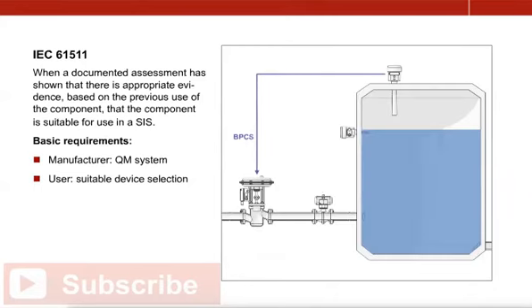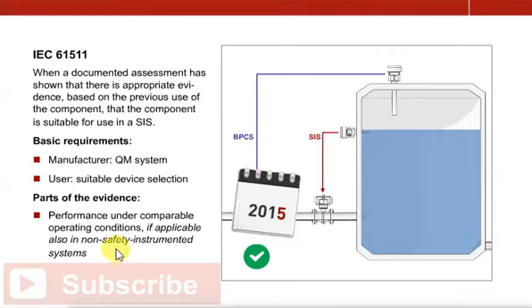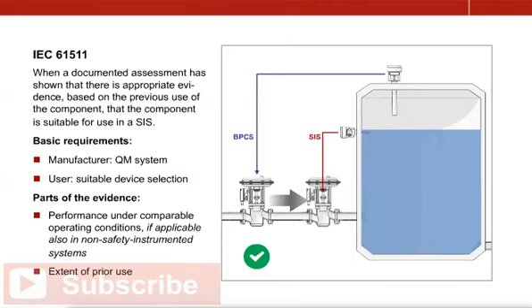Users are responsible for selecting a device that fulfills the fundamental requirements of their specific application. The documented assessment of prior use allows users to draw a device's suitability for use in safety instrumented systems under comparable operating conditions. As field units used in non-safety instrumented systems basically fulfill the same function, the experience gathered in these applications can be applied as well. If prior use of a device has reached a certain extent, and the device has shown a satisfactory performance, the user usually adds it to a list of standard devices. As part of an ongoing updating process, devices with an insufficient performance are removed from this list again.